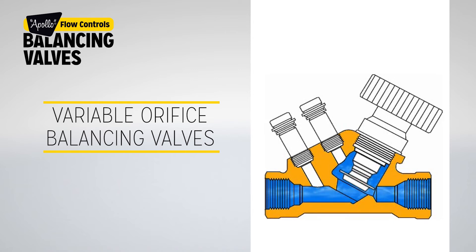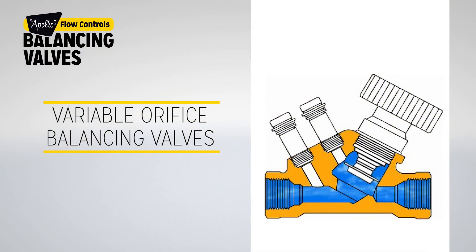The measuring accuracy of the variable orifice valve is adversely affected by this principle; the valve is accurate to plus or minus 15 percent dependent on the opening position. The valve is unidirectional, and the direction of the flow arrow on the valve body should be respected. The setting procedure is a time-consuming process to correctly set the valve at the balancing stage.